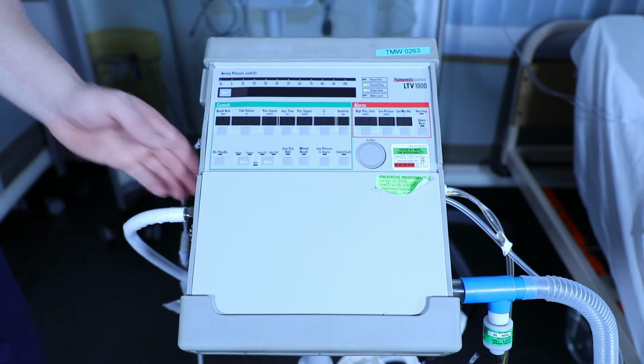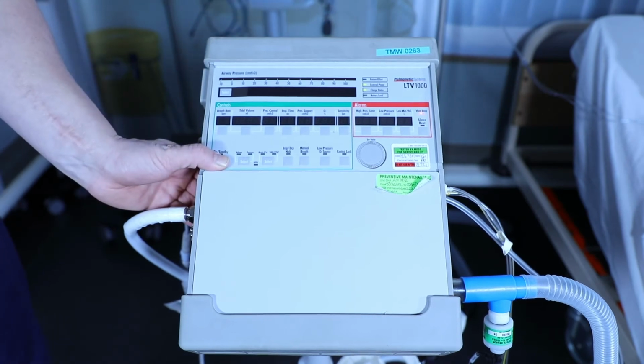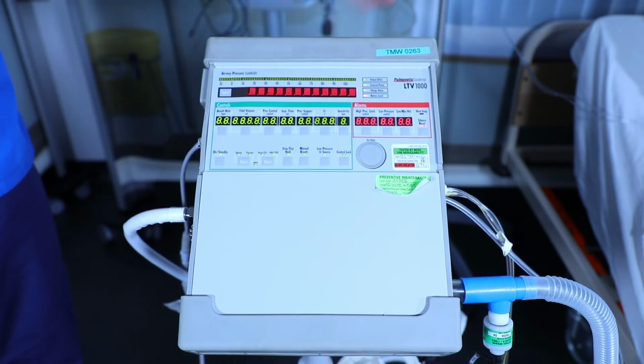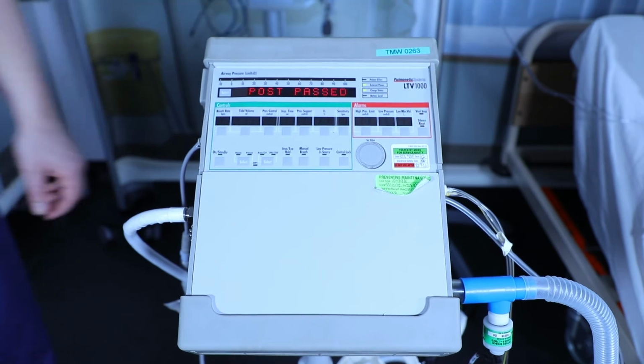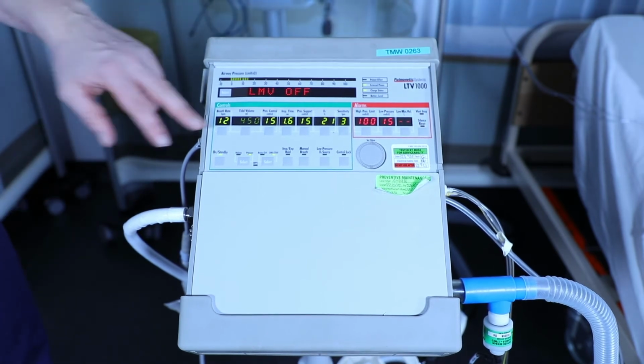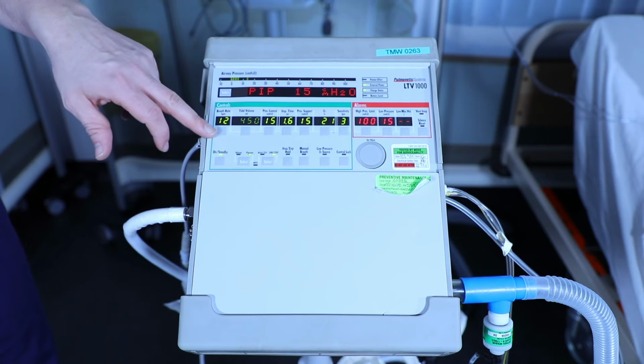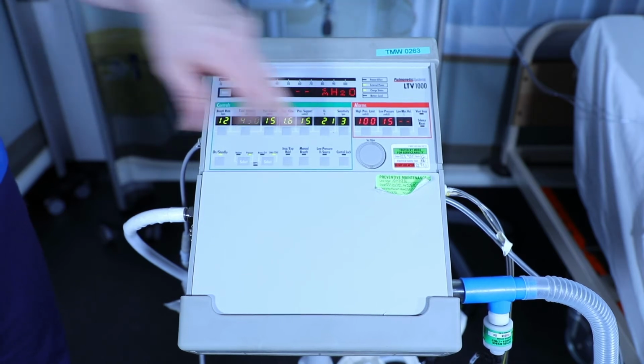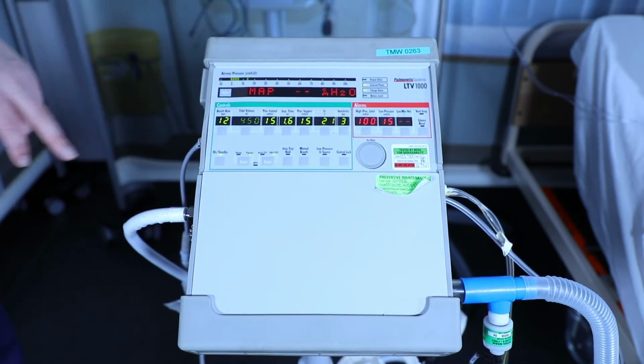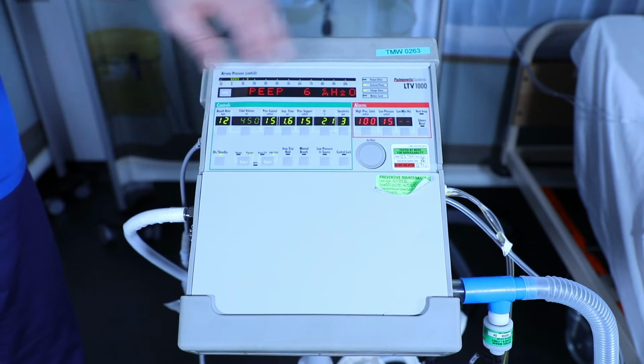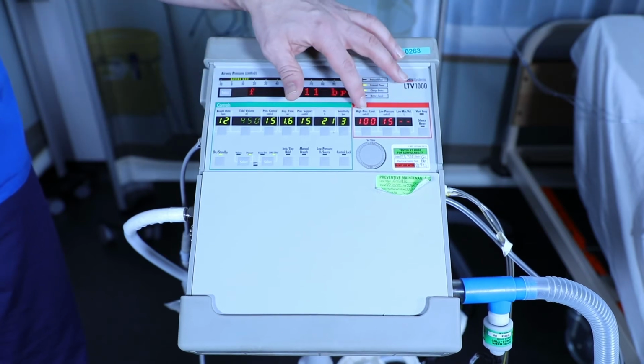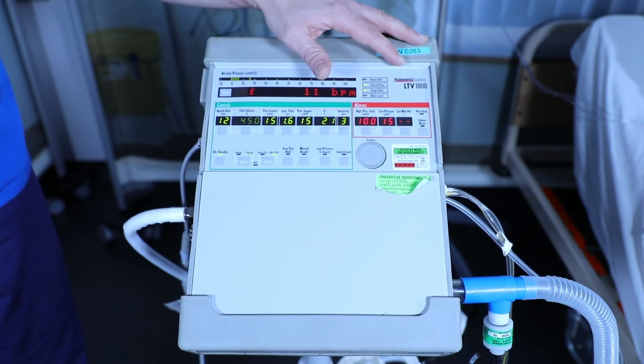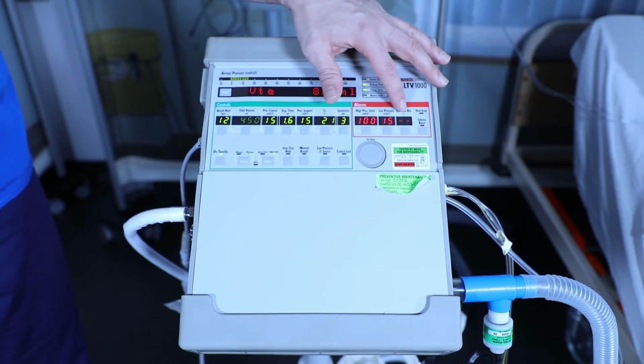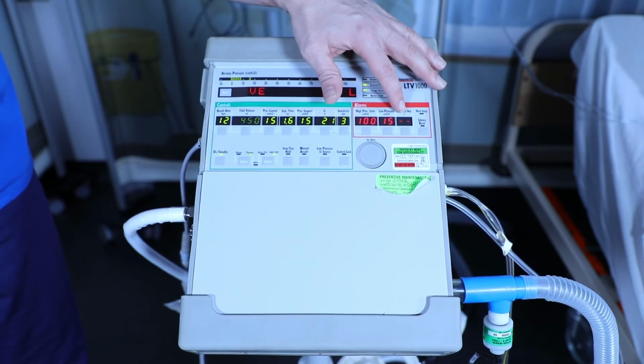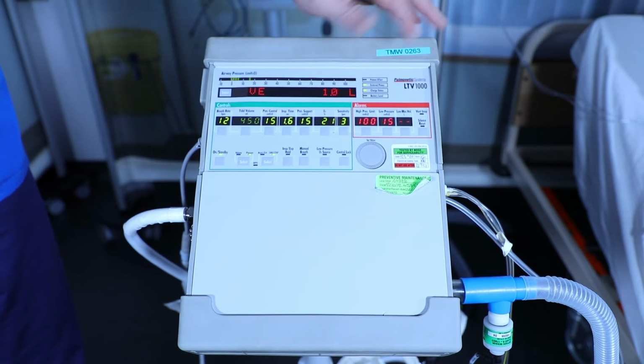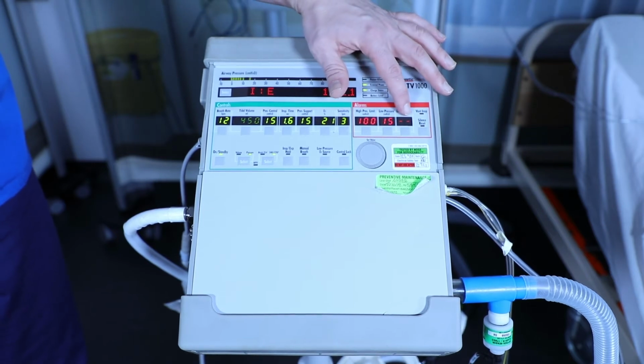So we'll switch the ventilator on in ventilation mode, so just press the on off button. You see all the LEDs illuminate except for the vent op. Now the ventilator defaults back to its previous settings depending upon which was already set. For the purpose of this video, we'll keep the high pressure limit above 100, and if we have erroneous alarms, we'll just change these so that the ventilator doesn't alarm. But of course these would be set appropriately for your patient.